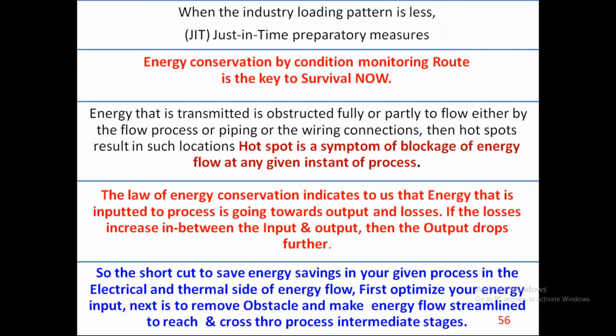So ultimately, this energy monitoring is a just-in-time preparatory measure for the process. It is a retrofit to the existing process. So energy conservation by condition monitoring is the key to survival now for the given industry. Whatever energy is transmitted from end to end, from the EB incoming to the delivery point at the tail end machine, wherever it is obstructed, either fully or partly, that is a hotspot. And that is a blockage of energy flow, meaning it is a loss to the industry. That has to be spotted by the infrared thermal imager only. A hotspot is a symptom of inefficiency or energy blockage, or energy partly blocked.